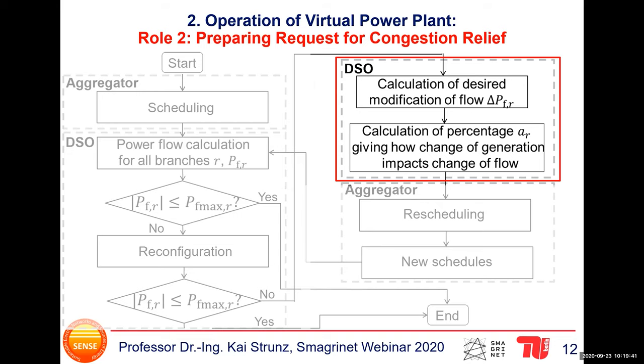Well, we can try to get help from the aggregator or the virtual power plant. To do so, the DSO, who has the information of the network and the buses, and knows the impedances of the network, calculates what needs to be done to relieve the congestion. Knowing the impedances, it can calculate so-called sensitivities. It can calculate by what percentage the generation at a certain bus needs to be modified in order to relieve the congestion. And it will convey this information to the aggregator, and the aggregator can now try to see whether it is able to deliver a service and change its generation portfolio in order to relieve the congestion.